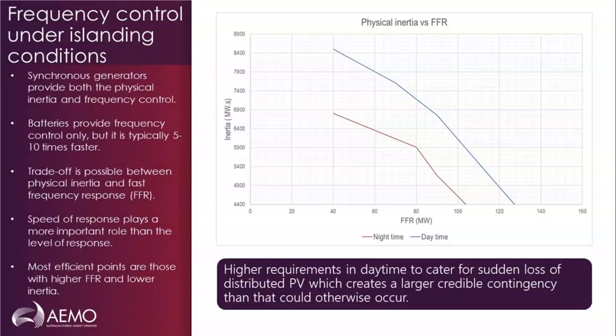The expected or unexpected response of this fleet to a credible contingency event would mean that we have a contingency larger than the largest credible contingency that we would have otherwise catered for. And to make sure that we can maintain the overall system security, and in particular in this instance the frequency, within the frequency bands, we need to have higher levels of FFR as well as higher levels of physical inertia to be able to secure the system, whether a contingency happens in daytime or nighttime.